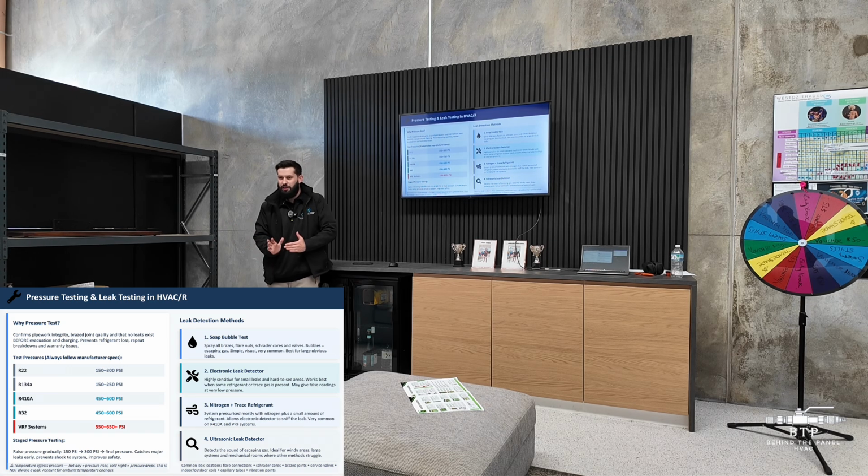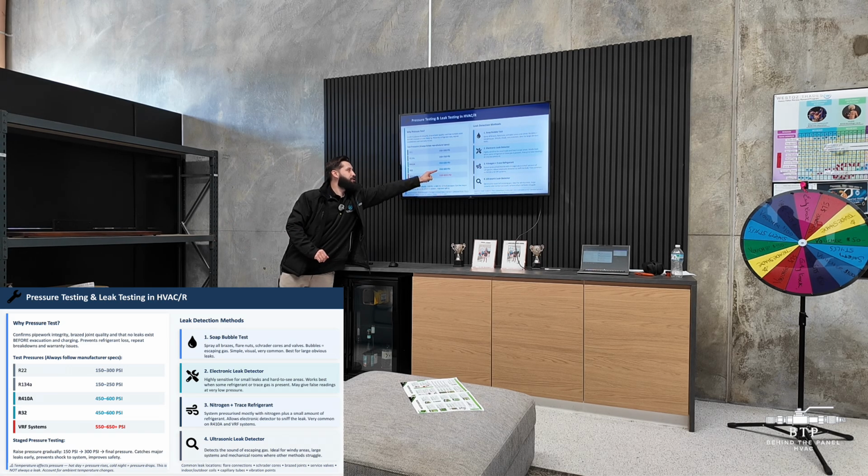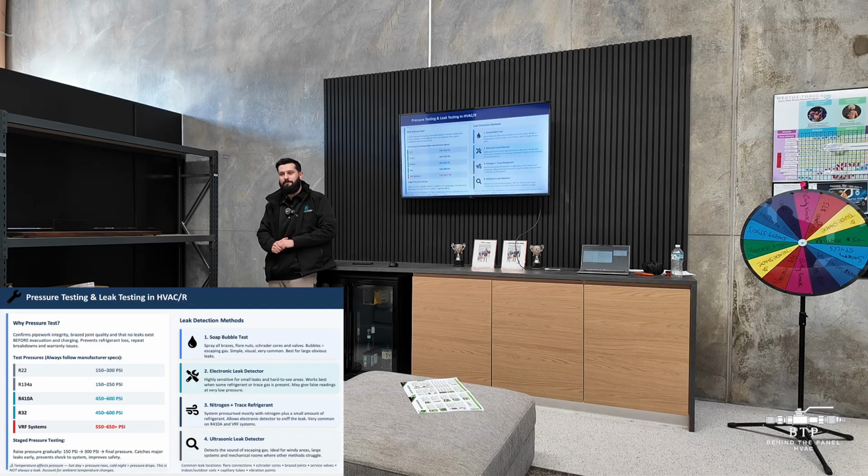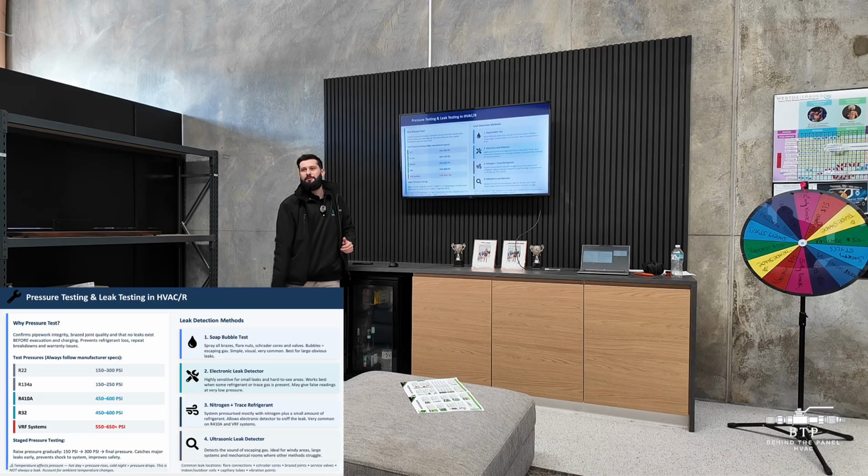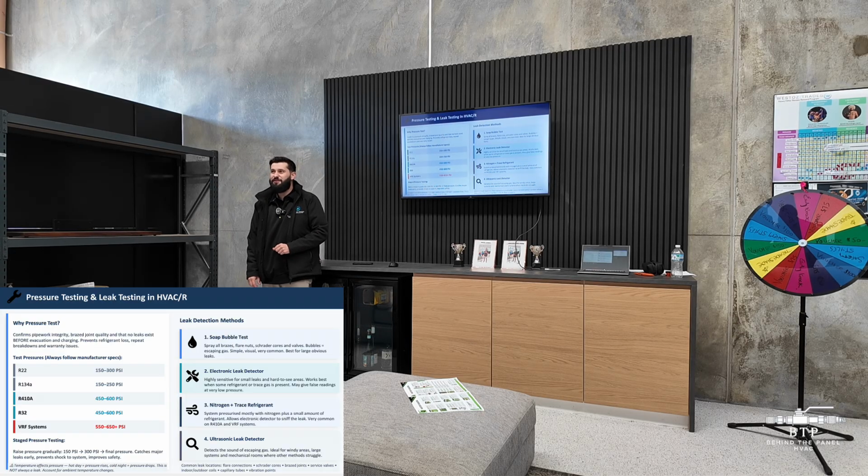Slowly increase the pressure up to the point where it reaches 450 to 600 psi. Very important, especially for the younger guys. Don't just go straight to 600 psi. Never do that.